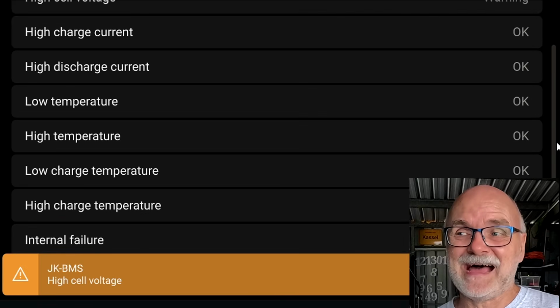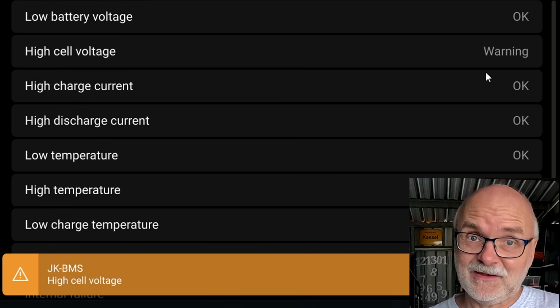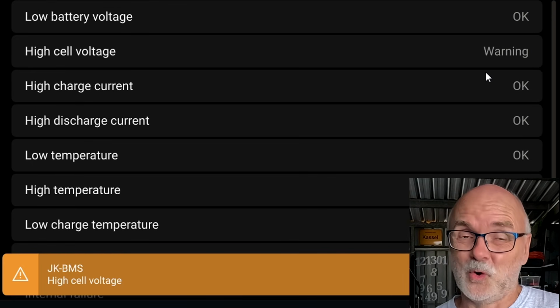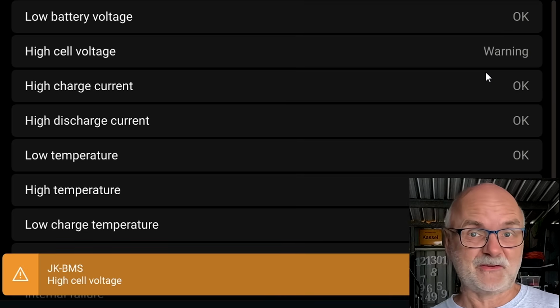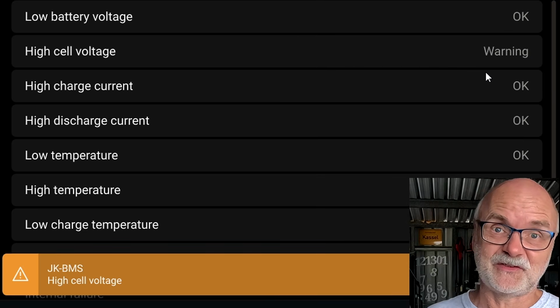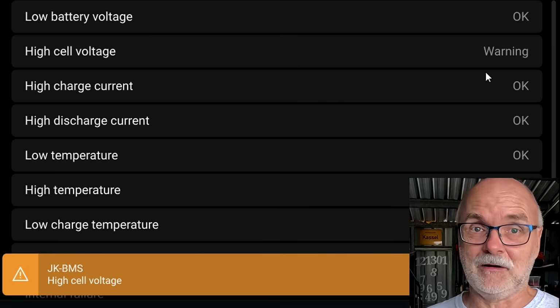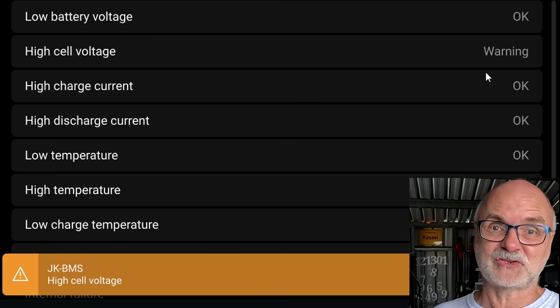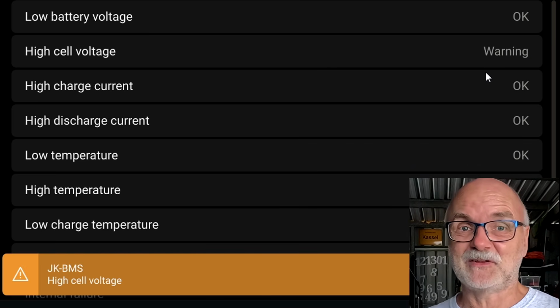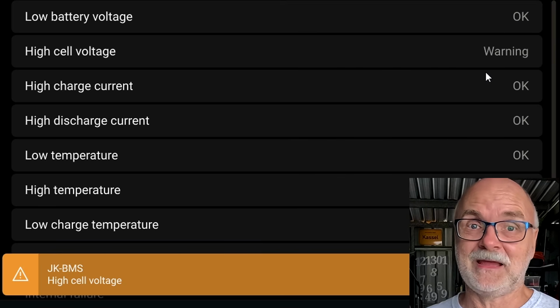It is not an alarm as such. So Victron and your inverter will distinguish between warnings and alarms. Warning is just the first step. Yeah, something in your system is wrong, but it is not severe. At this moment, we've got an overvoltage protection. The BMS has correctly messaged this to the master BMS, and it is reporting a warning to your inverter.